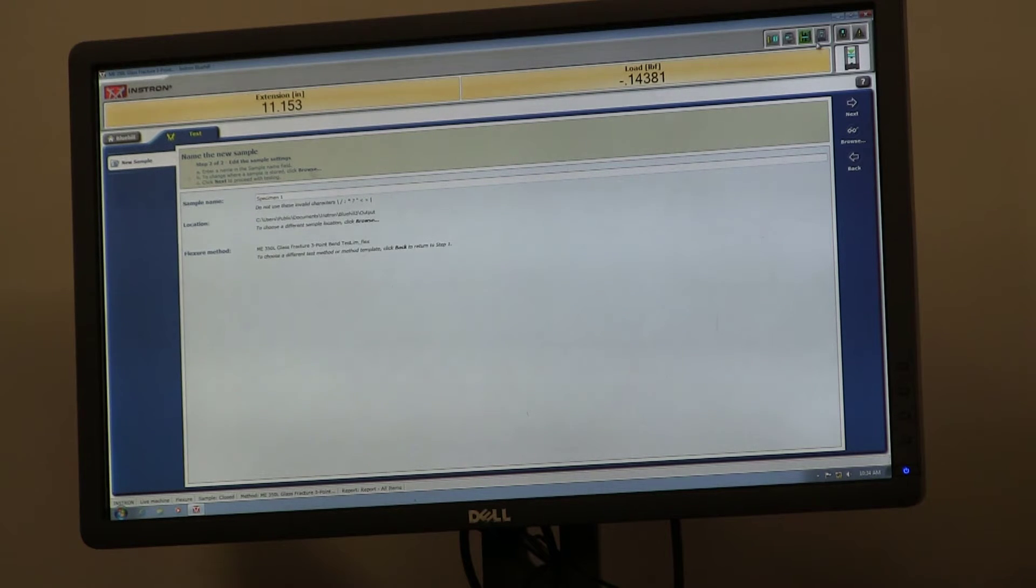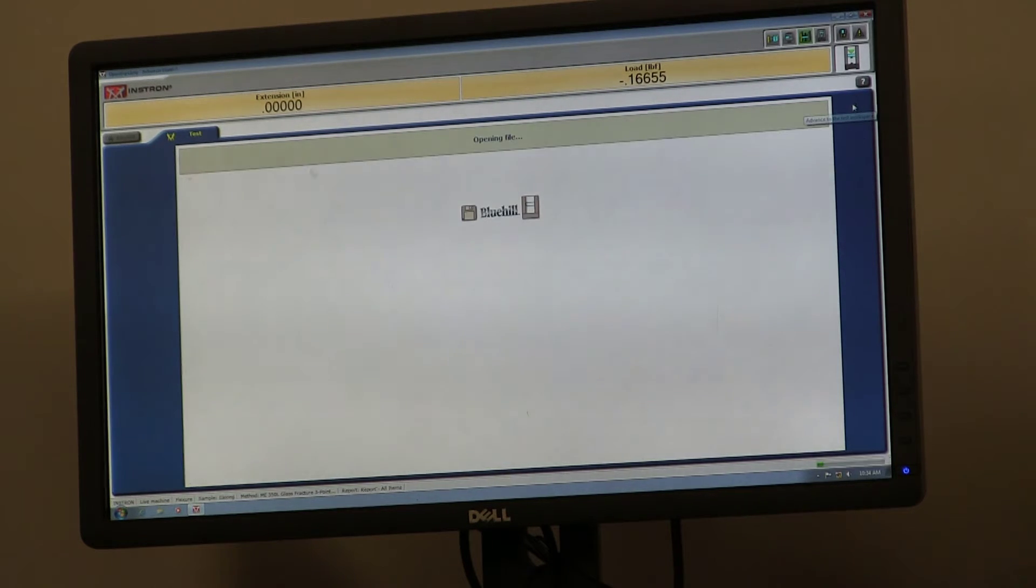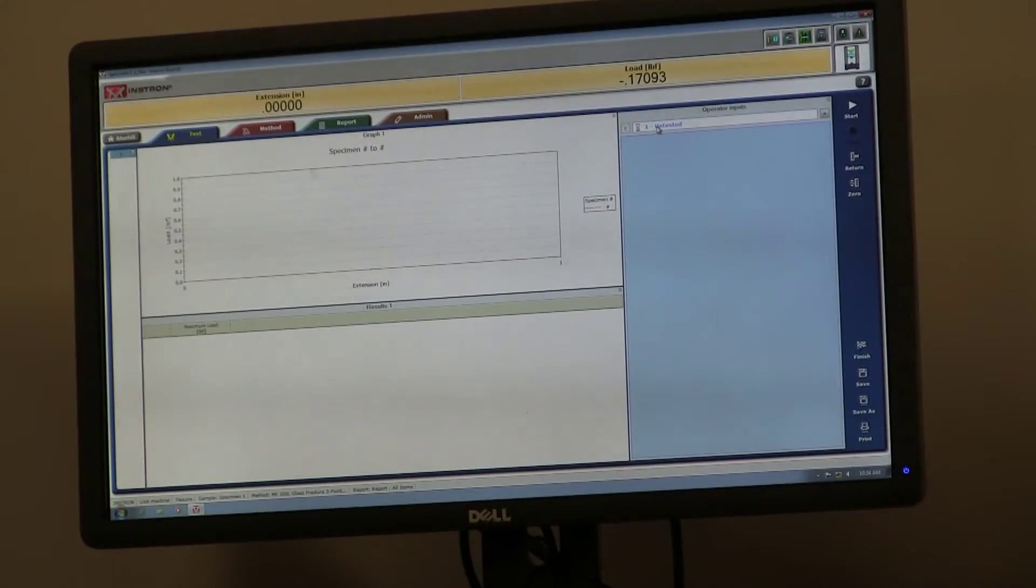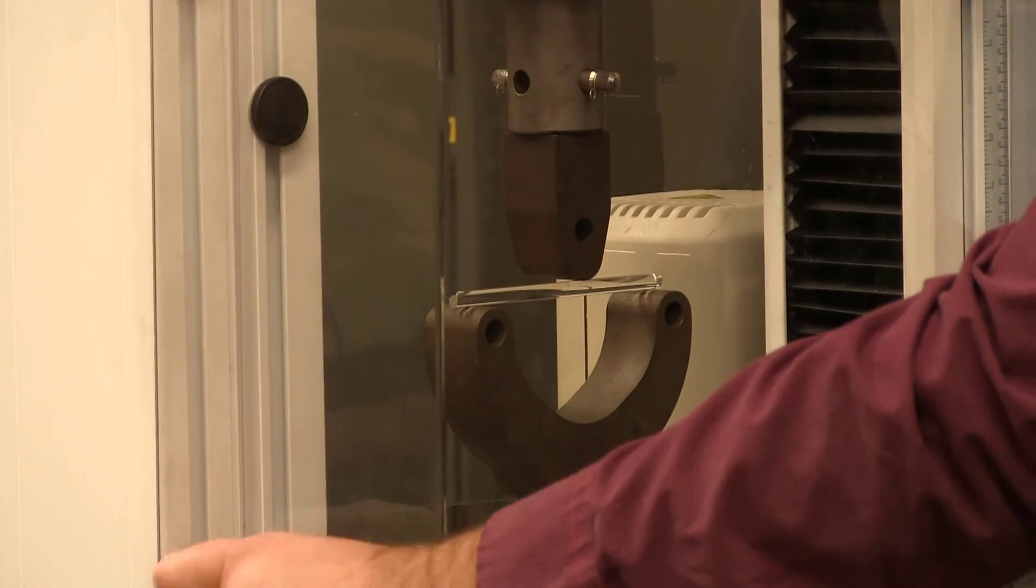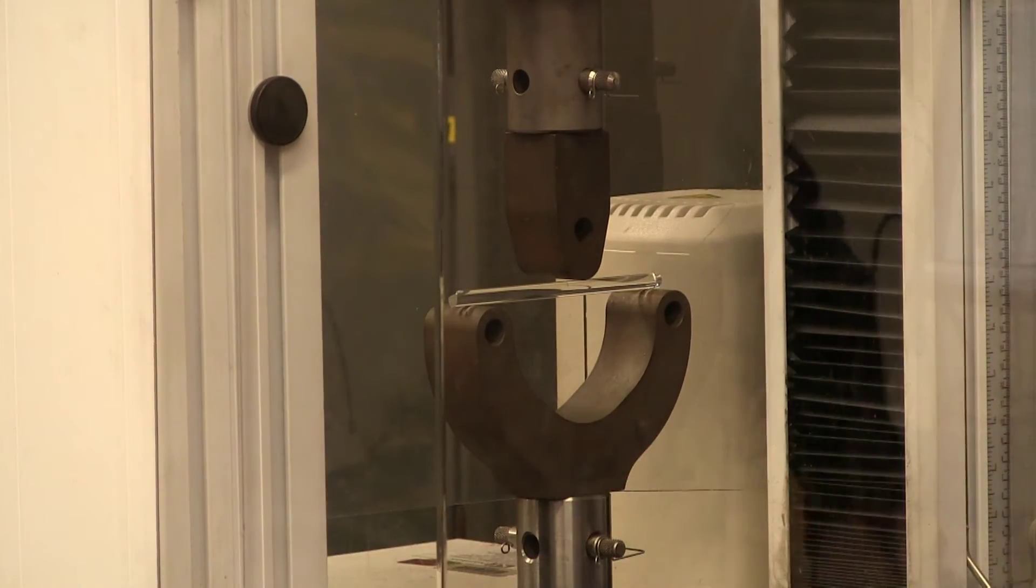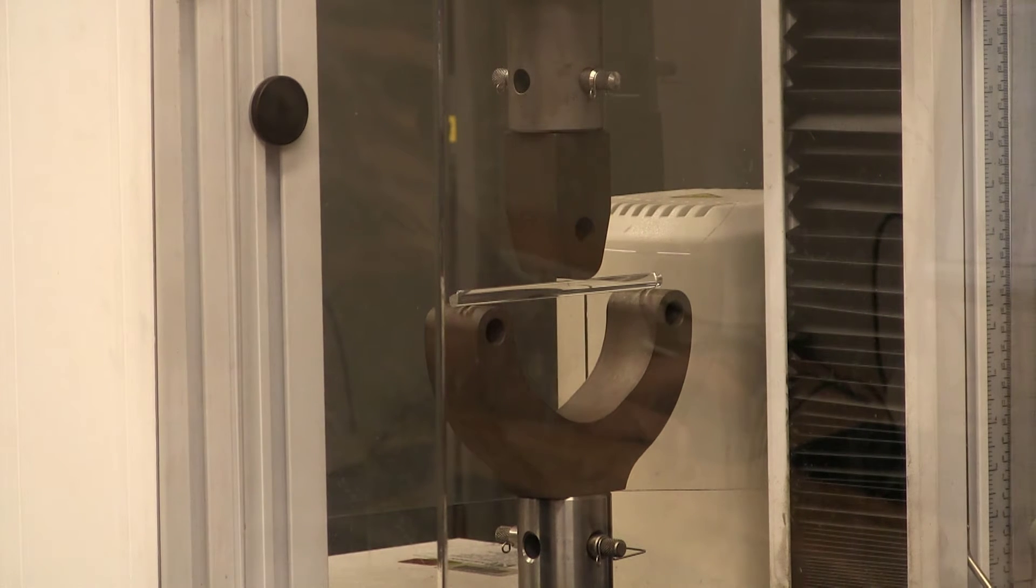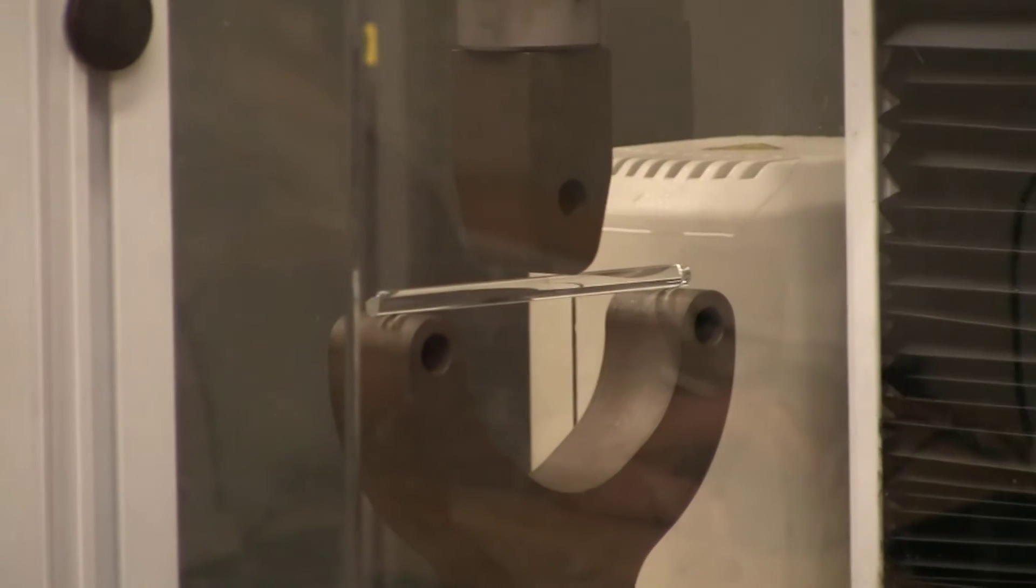And I'm going to zero the extension so that for my next specimen, I can just push return and it'll go back to here. And now we're ready to run our specimen. I put down the specimen name here. I'm going to push next, and we're ready to test. And at this point, I'm going to lower the shield, and I'm going to push run on the machine.